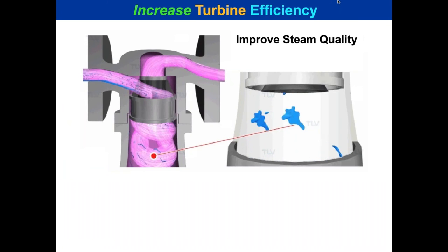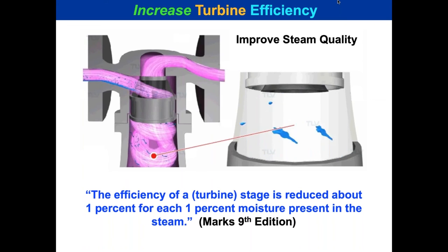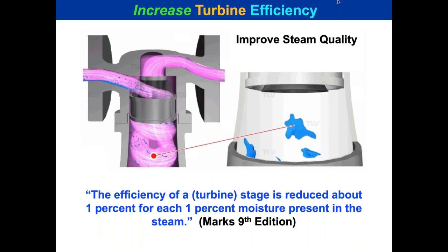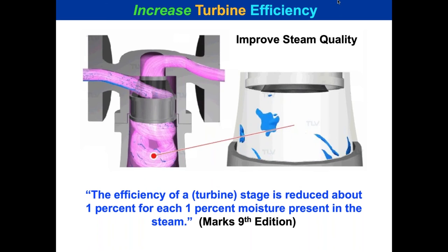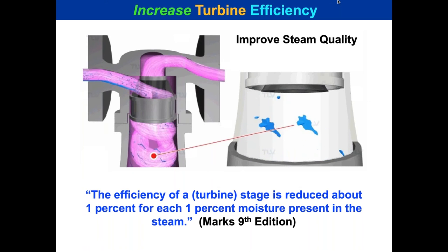We like to use separators on turbines. According to Marks, the efficiency of a turbine stage is reduced about one percent for each one percent of moisture. Why would you install equipment and deliberately reduce its efficiency? A separator doesn't reduce steam used but improves reliability. TLV separators achieve at least 98% moisture removal, bringing you to 99.7% or higher dry steam.